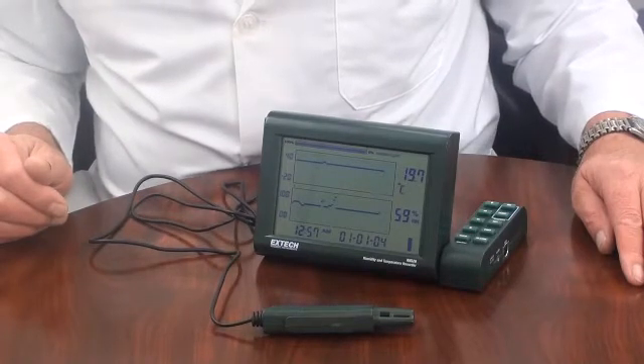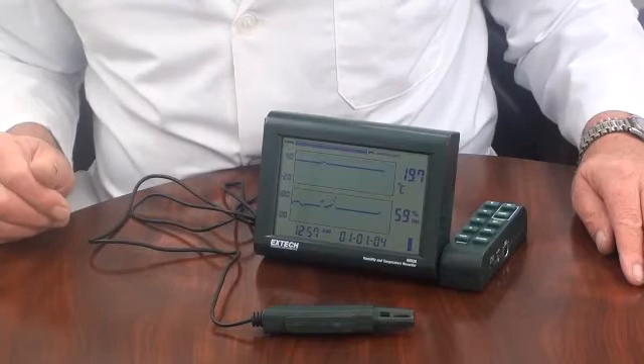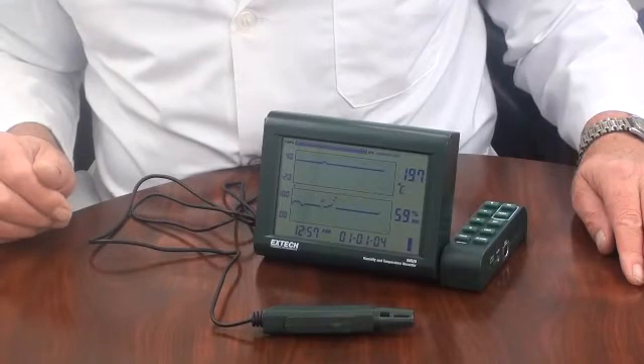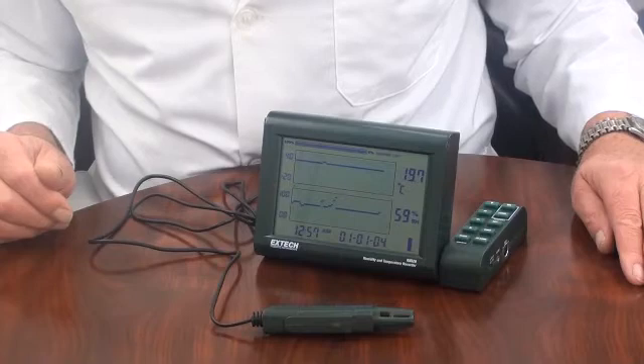The user can program the sampling rate and the high and low alarm parameters. The defined parameters are a delayed start time, setting the logging rate from every 6 seconds up to every 3 hours, and a minimum and maximum alarm limit for temperature and humidity.